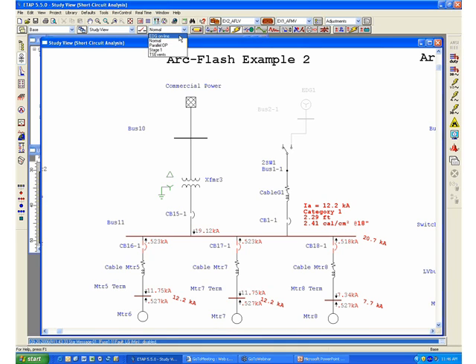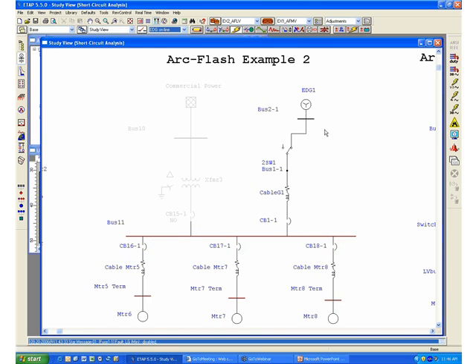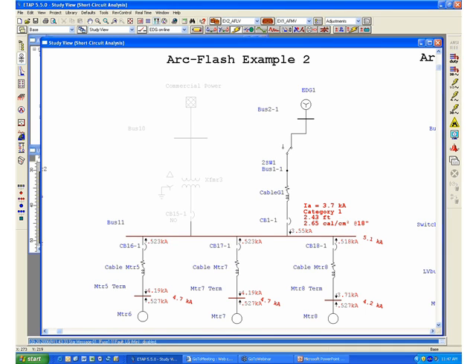At this point, if we rerun the ArcFlash calculation, we can see that the program has determined a similar value for the category, still a category one on the main switchgear here.